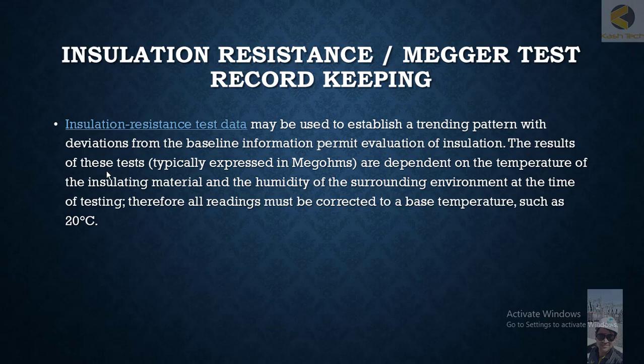The results of these types of tests, typically expressed in megaohms, depend on the temperature of the insulation material and the humidity of the surrounding environment at the time of testing. Therefore, all records must be corrected to a base temperature such as 20 degrees centigrade.